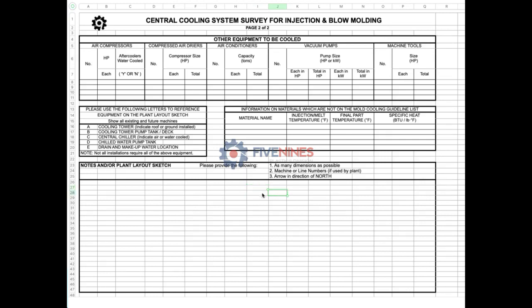So let's say you could just easily print out this sheet when you're done filling it out and just give a rough sketch of where your chiller or tower is. Maybe you've got a tower over here, chiller over here, and then just draw out where your molding machines or processing equipment are. Just draw a simple line where the runs are going, the channels, how many elbows, if you're so inclined, the diameter of the channels, so we can see if there's a pressure loss anywhere, starving machines in certain rows. That's very helpful.